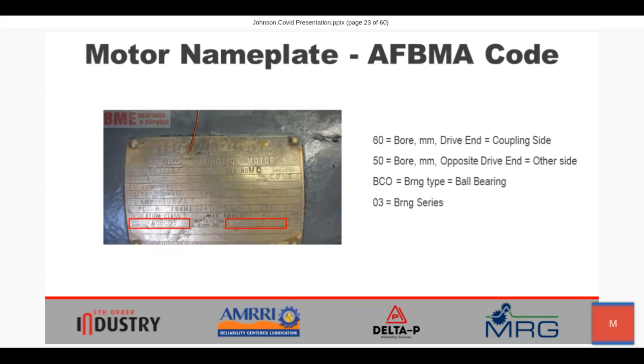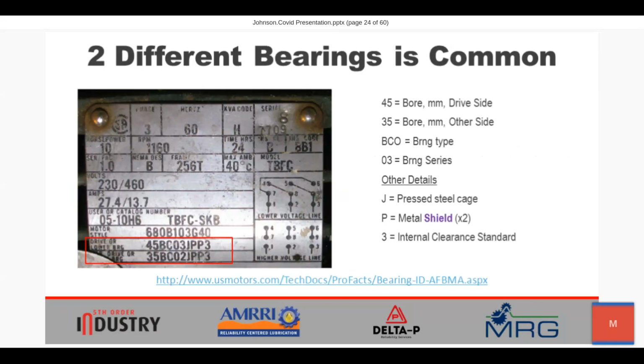BCO represents the bearing type identified, Conradson ball bearing, and 03 represents the bearing series or bearing grade. Here's another example, a different motor nameplate using a similar naming structure with a few extra details.